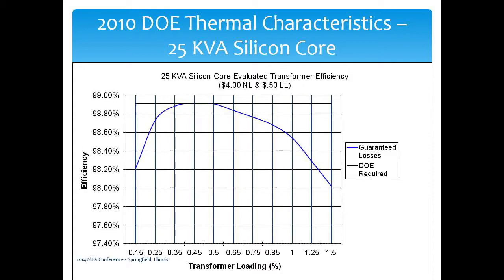Now when DOE first came out, there were some gray areas, and some manufacturers took it upon themselves to say the only area I have to be concerned about is this 50% load. And so you can actually design a transformer to start off way down here and kind of ramp up and then ramp back down very quickly. And that's a very narrow window. And of course what happens is you don't put as much core steel in it. Your core saturates, your losses go up higher.